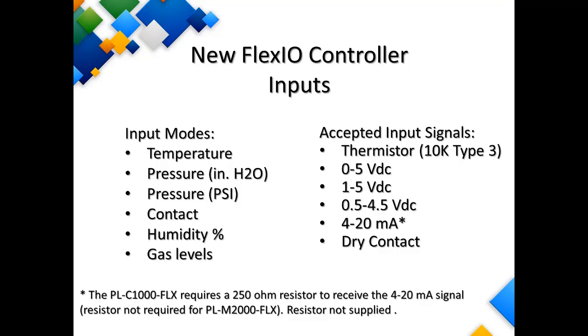And as you'll see, beside the 4 to 20 milliamp, there's a little asterisk. We just want to point out that if we want to use the 4 to 20 milliamp signal on a C1000 platform, we will need a 250 ohm resistor to be able to convert the signal. Now, just keep in mind that if we're using the M2000 version, we do not need that resistor. So it is essentially native to the controller.